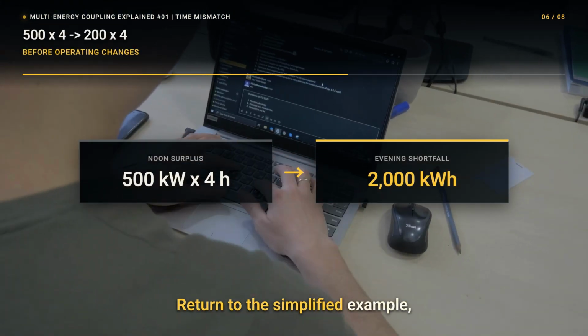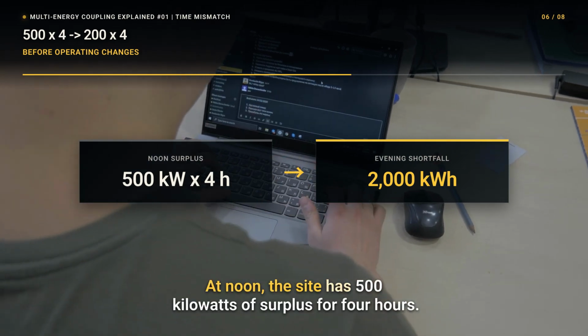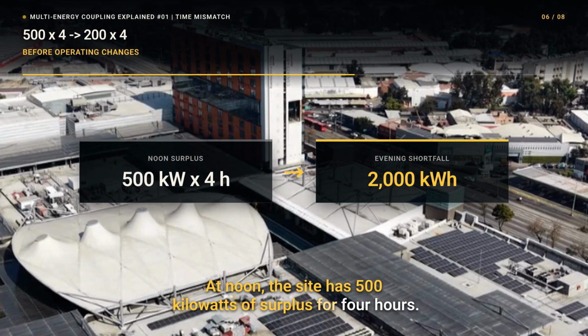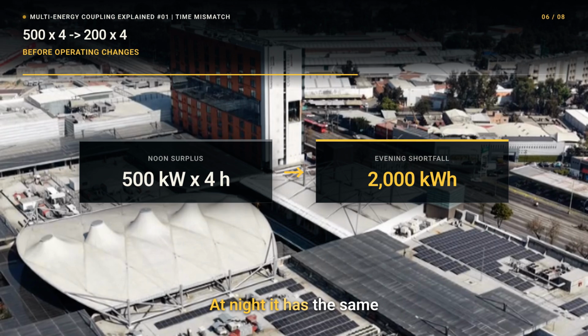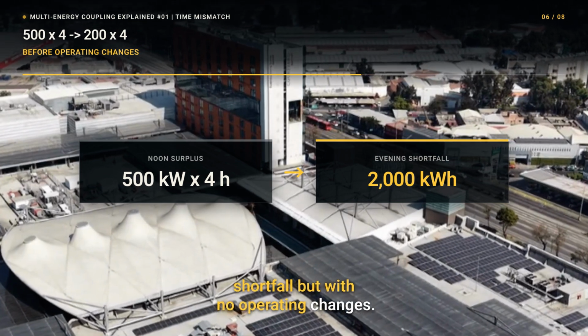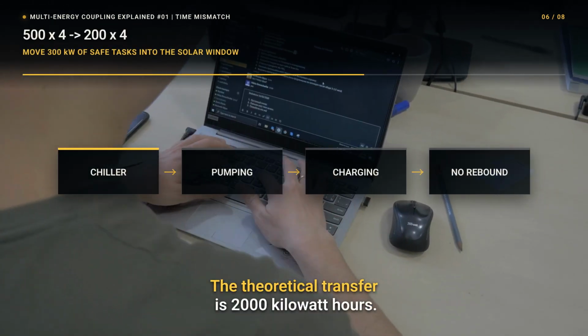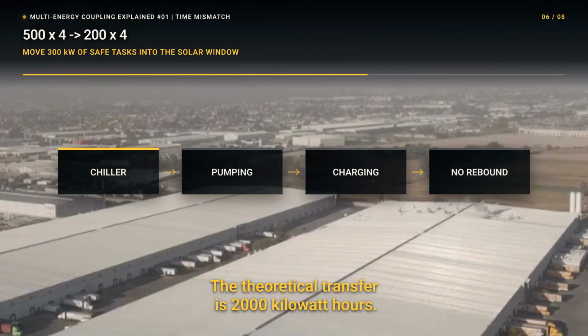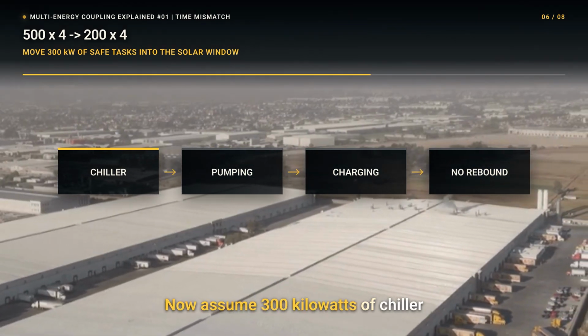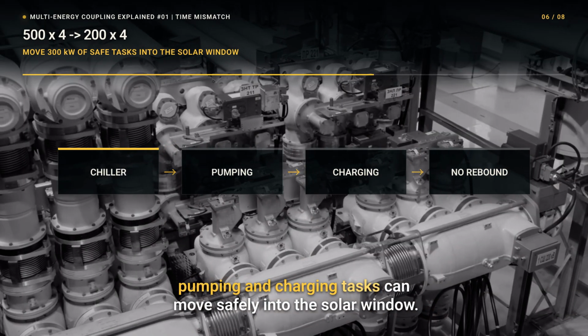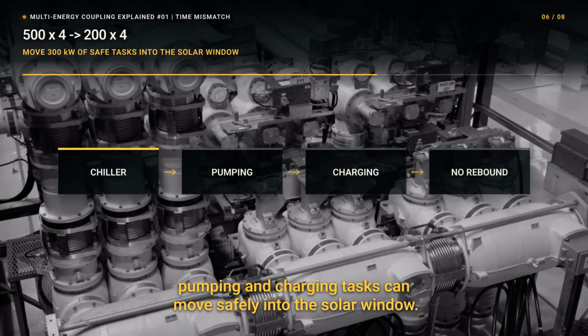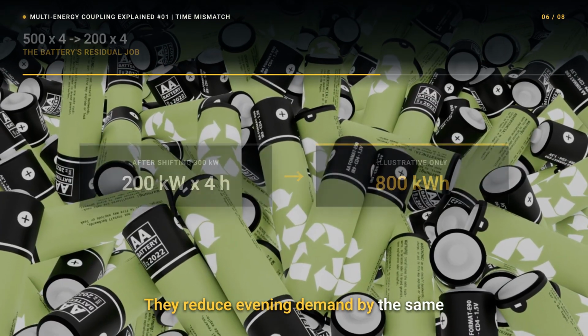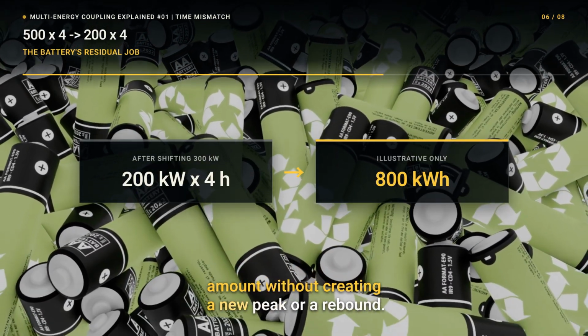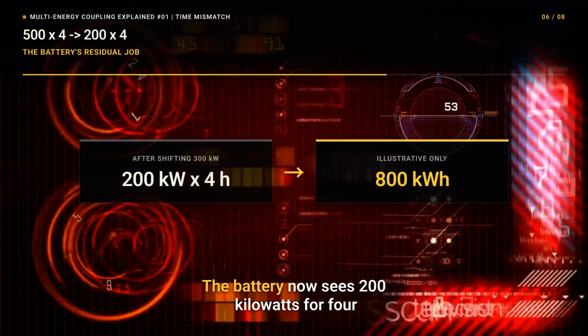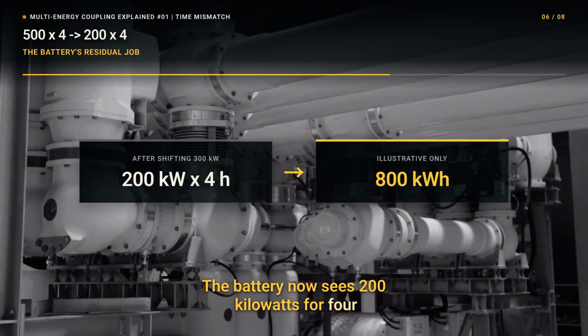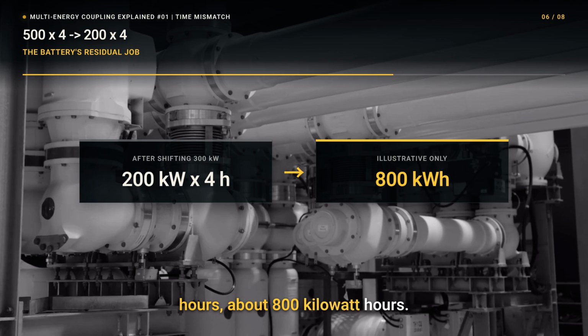Return to the simplified example. At noon, the site has 500 kilowatts of surplus for 4 hours. At night, it has the same shortfall. With no operating changes, the theoretical transfer is 2,000 kilowatt-hours. Now assume 300 kilowatts of chiller, pumping, and charging tasks can move safely into the solar window. They reduce evening demand by the same amount without creating a new peak or a rebound. The battery now sees 200 kilowatts for 4 hours, about 800 kilowatt-hours.